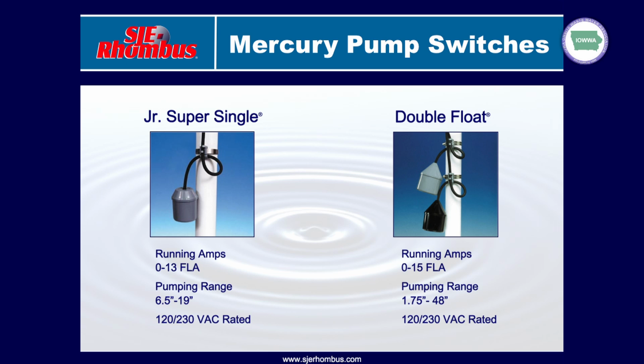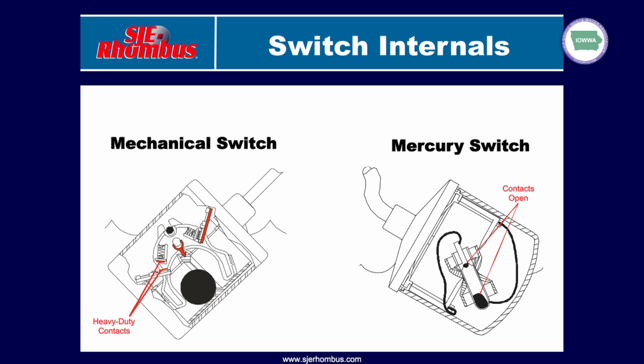All right, here's just a couple of the different floats that we make in the mercury style pump switches. We offer a traditional single float option as well as a double float. Most people have not seen the inside of a switch without cutting it open, so this slide gives you some idea of what's going on inside a mechanical switch. This is one way of doing it, where you've got a ball in a raceway. As the float moves up or down, that ball moves through the raceway and actuates a lever that engages or disengages the contacts inside the mechanical float.